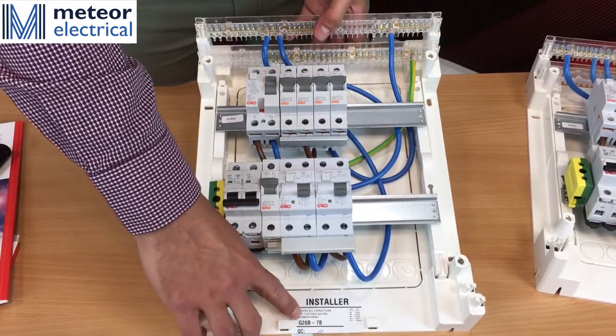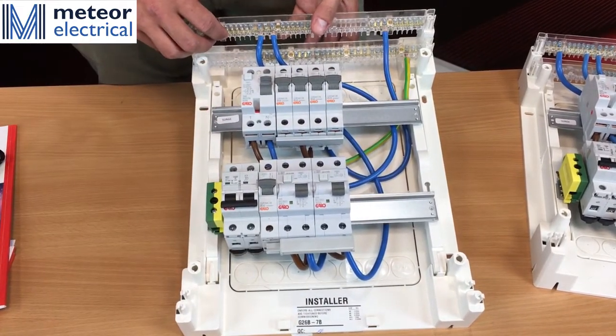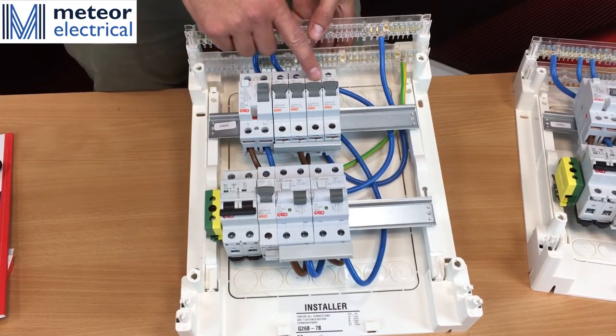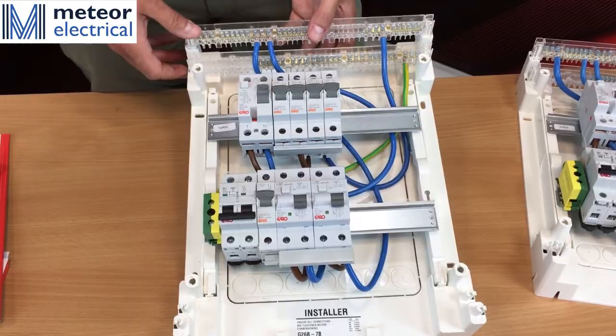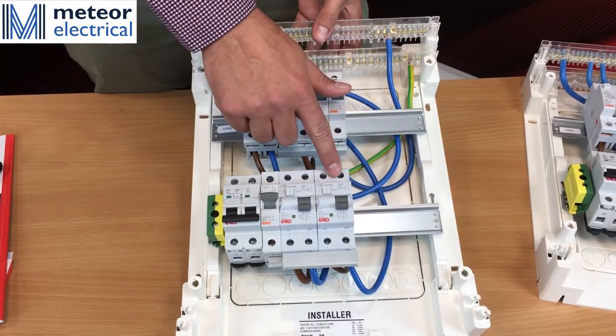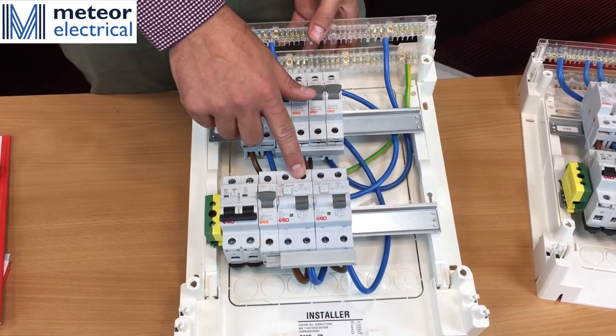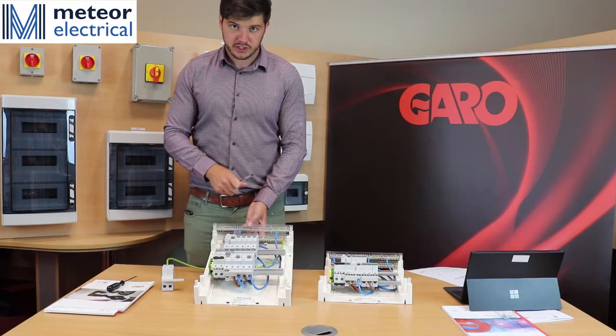The second option then is the G26B-78. As before, we have your MCBs protected by your RCD, which would be your ring main circuits. For the luminaire circuits, there are individual RCBOs. The advantage of this board over the other is that the luminaire circuits are protected individually, which helps for safety purposes.